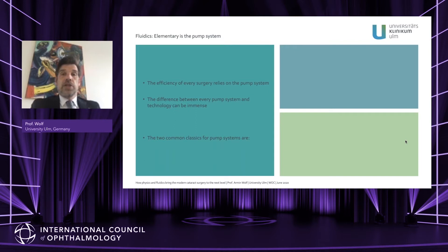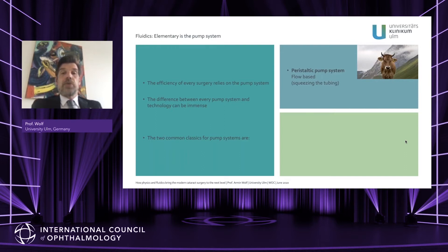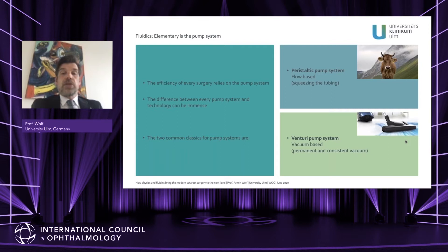Basically speaking, there are two common pump systems for vitreoretinal and cataract surgery. The most established is the peristaltic pump system, which is flow-based — you can consider it as squeezing tubing, where you control the vacuum and it is flow-based. The older system is the Venturi pump system, which is vacuum-based; you have a permanent and consistent vacuum and you control the flow.